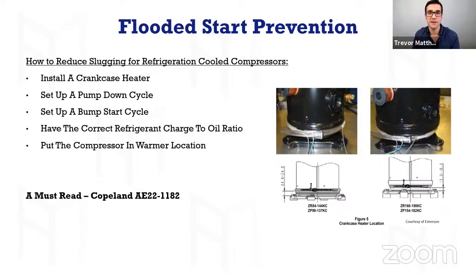Set up a pump down cycle. A pump down cycle is where you shut off a solenoid, we'll say, and it pumps all the liquid refrigerant out of the evaporator and all out of the suction, so you don't have any migration from the evaporator to the compressor.